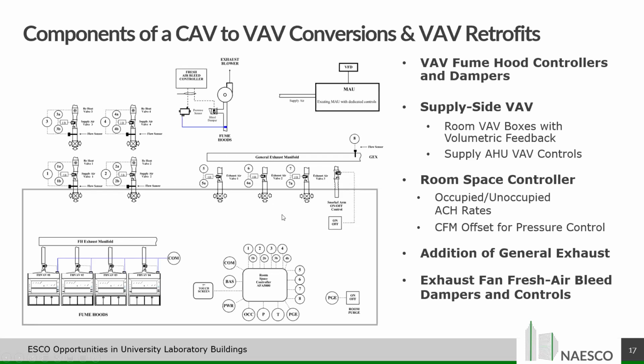If it's a CAV lab, constant air volume lab, you may need to add some general exhaust, but a lot of times it's there already, and you're either going to retrofit new valves into it or dampers and take control of those with new actuators. A lot of the older systems have pneumatics, believe it or not. There's still a lot of pneumatic lab control systems. So replacing those with electronic is always a key. And snorkels, you know, these snorkel exhausts are always constant air volume in labs, and they can be a significant increase. So just adding a damper or venturi valve in there and having either an on-off switch or a timer to control that is a great strategy.